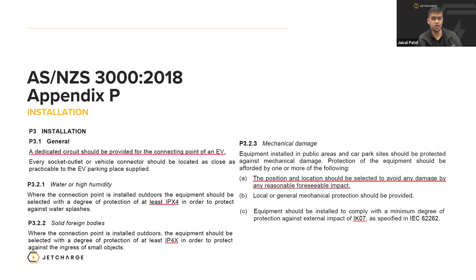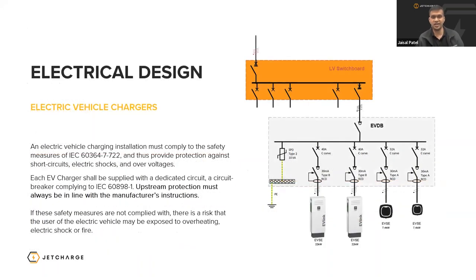If you are designing a charging system where there is a potential for rain and dust to come into the charging station, then you would have to design it to be at least IP44 rated. In public car parks or car parks prone to mechanical damage, where there's a risk of vandalism, you would have to position the chargers to avoid any reasonably foreseeable impacts, for example away from trafficable areas, or have bollards or wheel stops located so that they are protected against significant damage from other cars or people. They should also have a minimum IK rating of IK07 to protect against vandalism as well. Next slide, please. Now let's go into the electrical design.